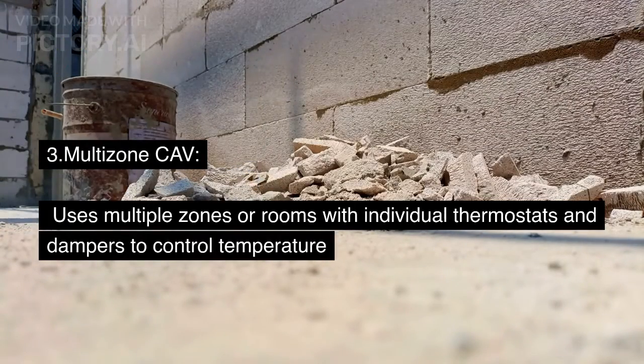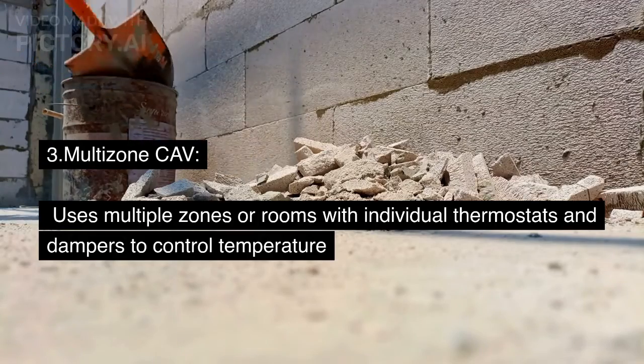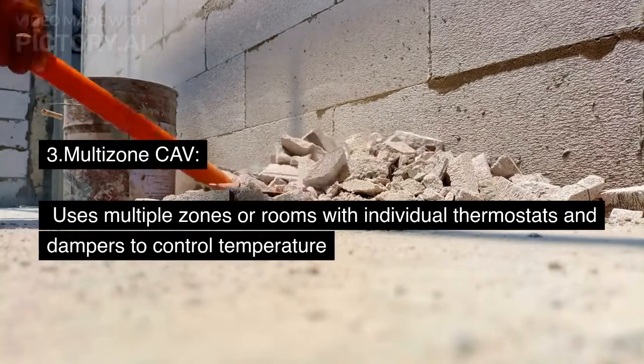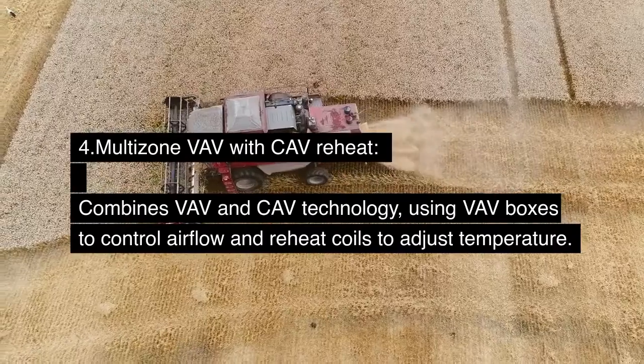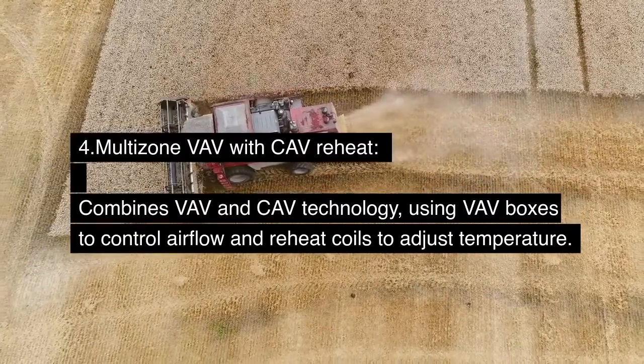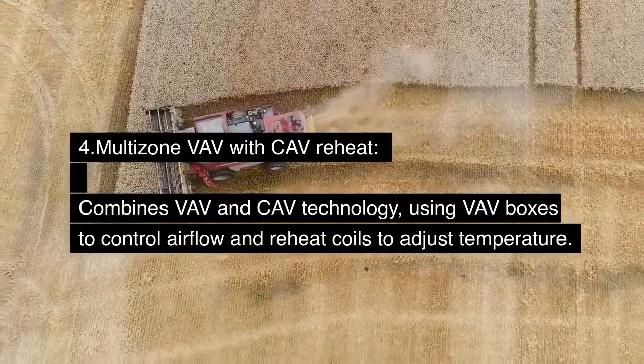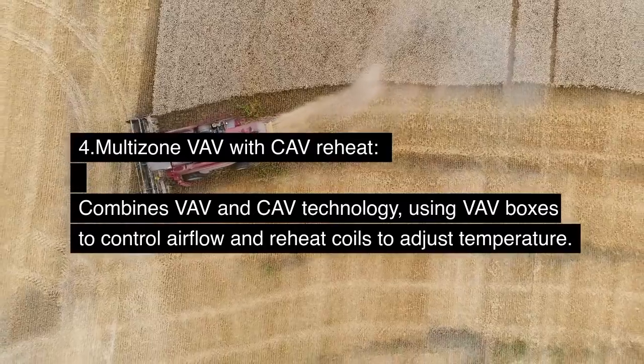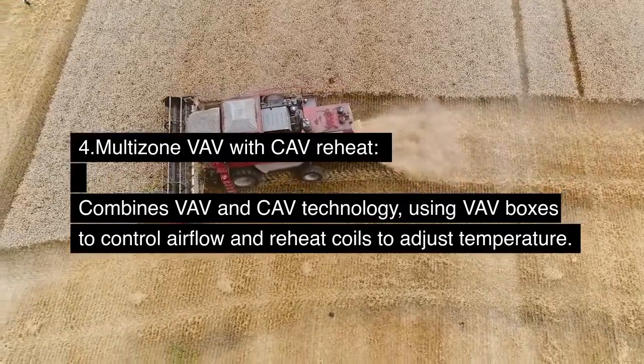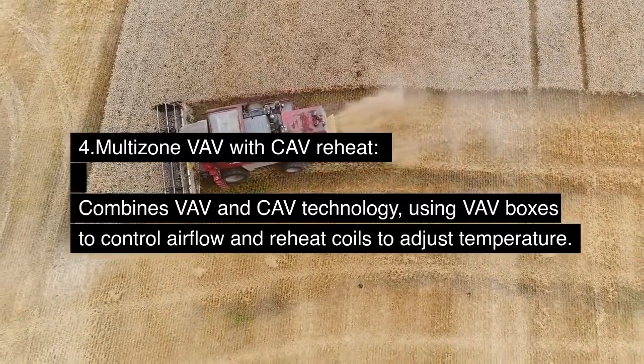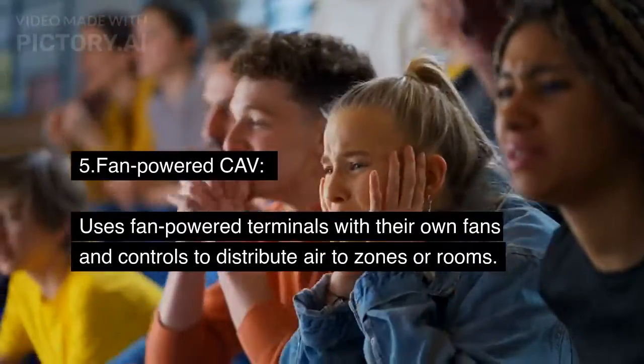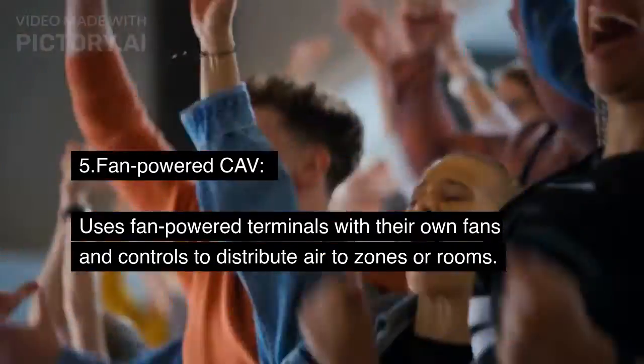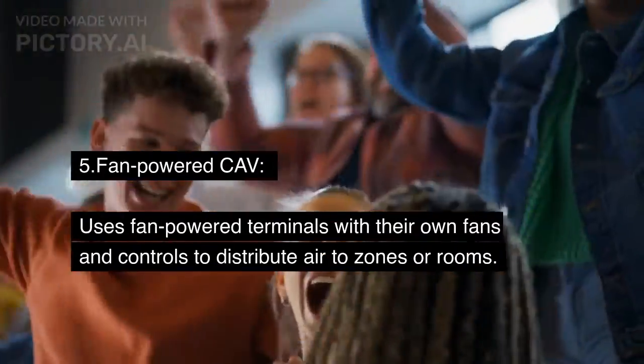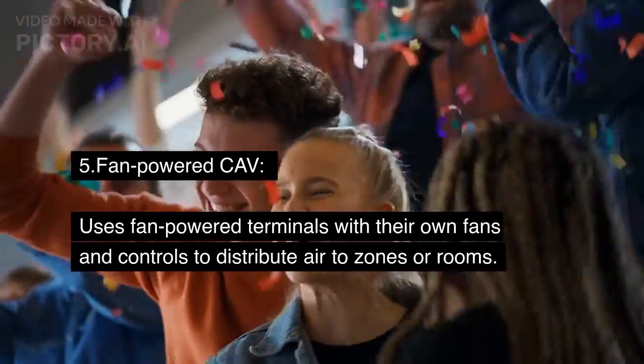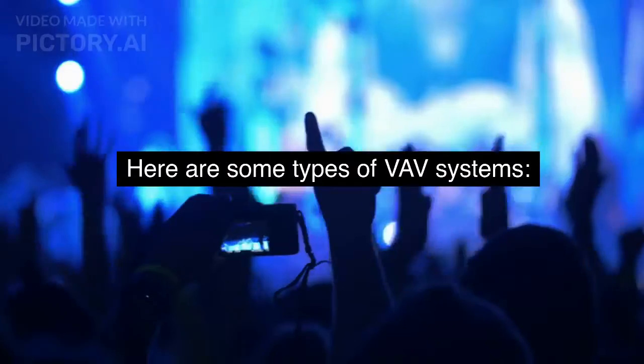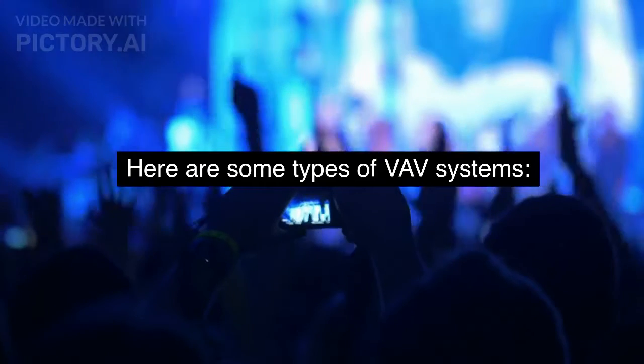3. Multizone CAV. Uses multiple zones or rooms with individual thermostats and dampers to control temperature. 4. Multizone VAV with CAV reheat. Combines VAV and CAV technology, using VAV boxes to control airflow and reheat coils to adjust temperature. 5. Fan-powered CAV. Uses fan-powered terminals with their own fans and controls to distribute air to zones or rooms. Here are some types of VAV systems.